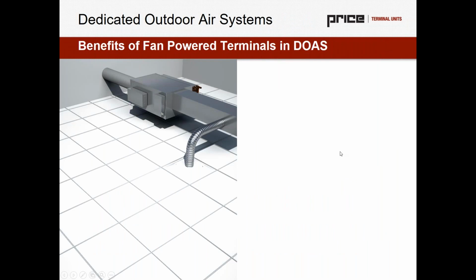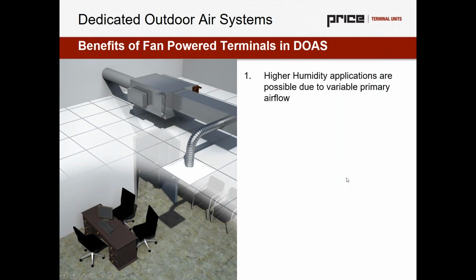There's lots of benefits of using this kind of configuration in a dedicated outdoor air system. One would be that higher humidity applications are possible, and that's really due to that variable primary air inlet. So the fact that primary air inlet can measure and monitor airflow in real time and provide a significant amount of turn down is going to allow for those blasts of higher volume dry outdoor air in some instances to condition higher humidity zones. Not something that's as critical for you guys in Seattle, but as we see this move its way definitely into the southeast, it will be a point of interest.